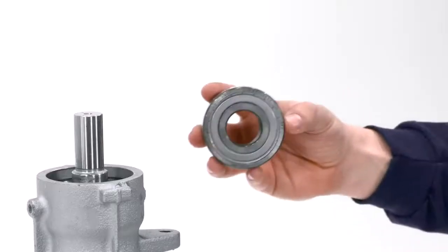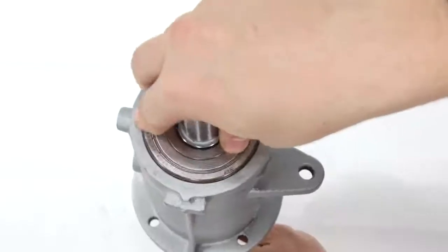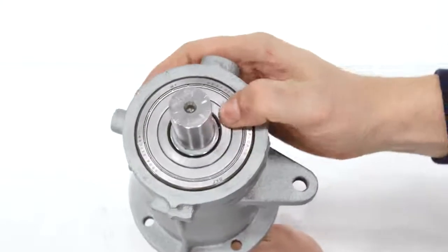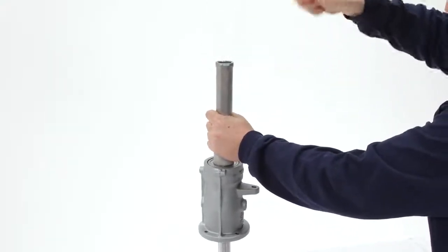Add the second bearing onto the shaft and into the top of the housing. Use an adapter and hammer if necessary to keep pressure on the inner race of the bearing as you guide it a little further onto the shaft.